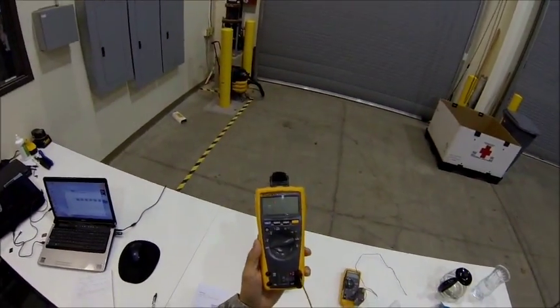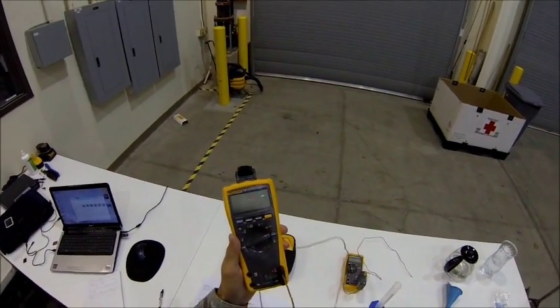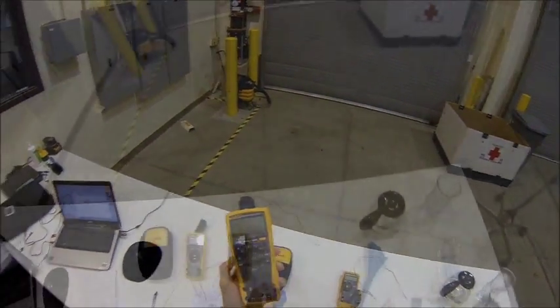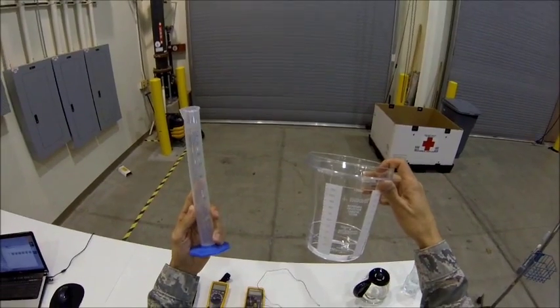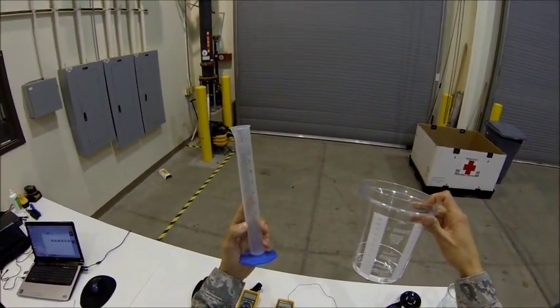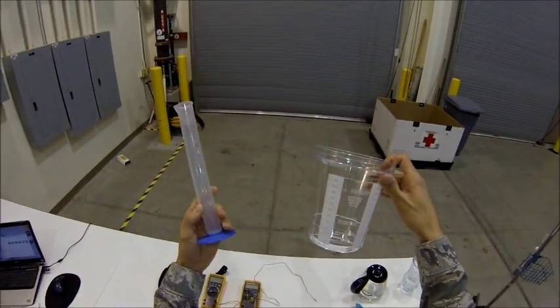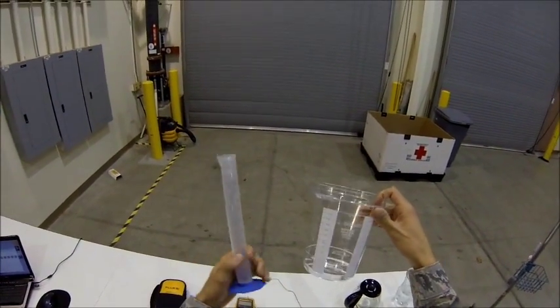You also need some form of a calibrated temperature monitor for the purpose of testing this unit. I like using the multimeter with attached thermocouple. You'll need containers, not only to catch the fluids for recycling into your testing, but you can also use it to check the flow rate. All you need is this unit with a graduated cylinder or a collection canister with measurement markings and a stopwatch.